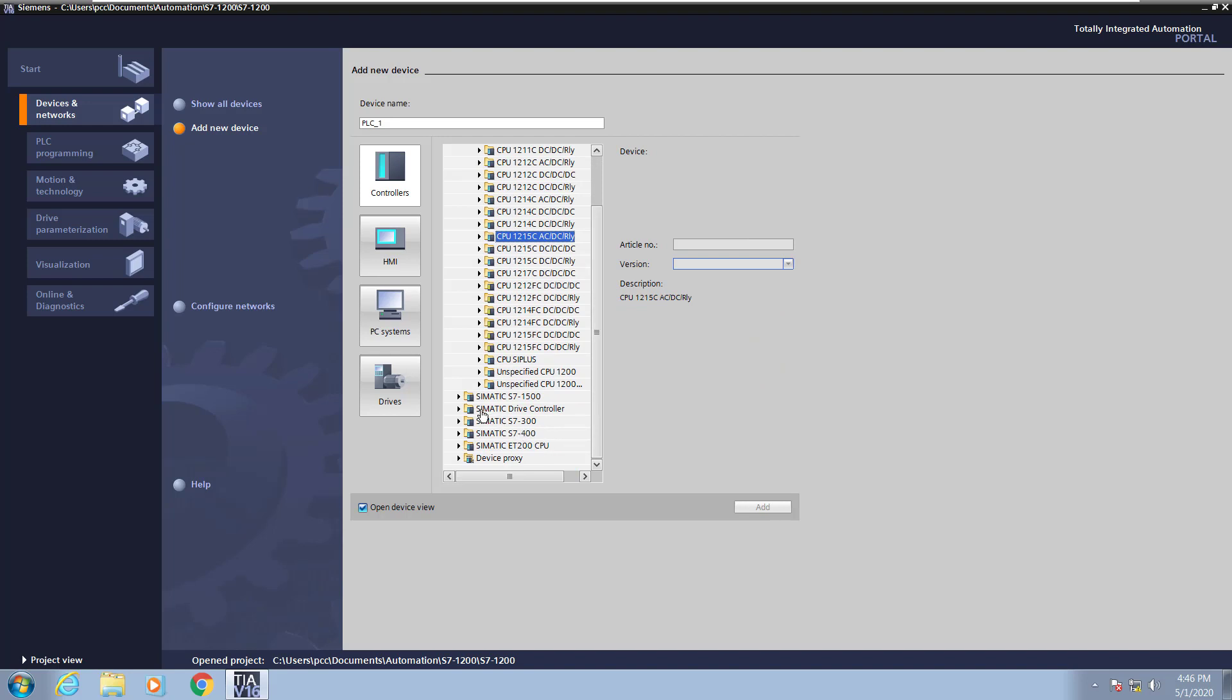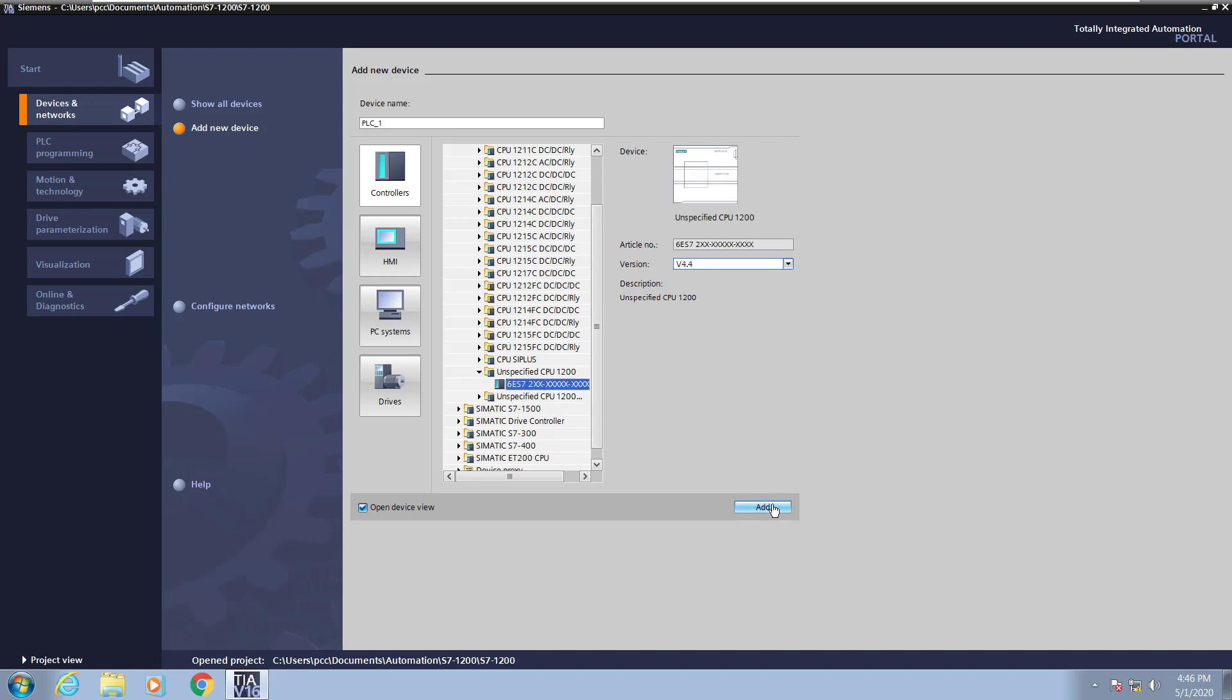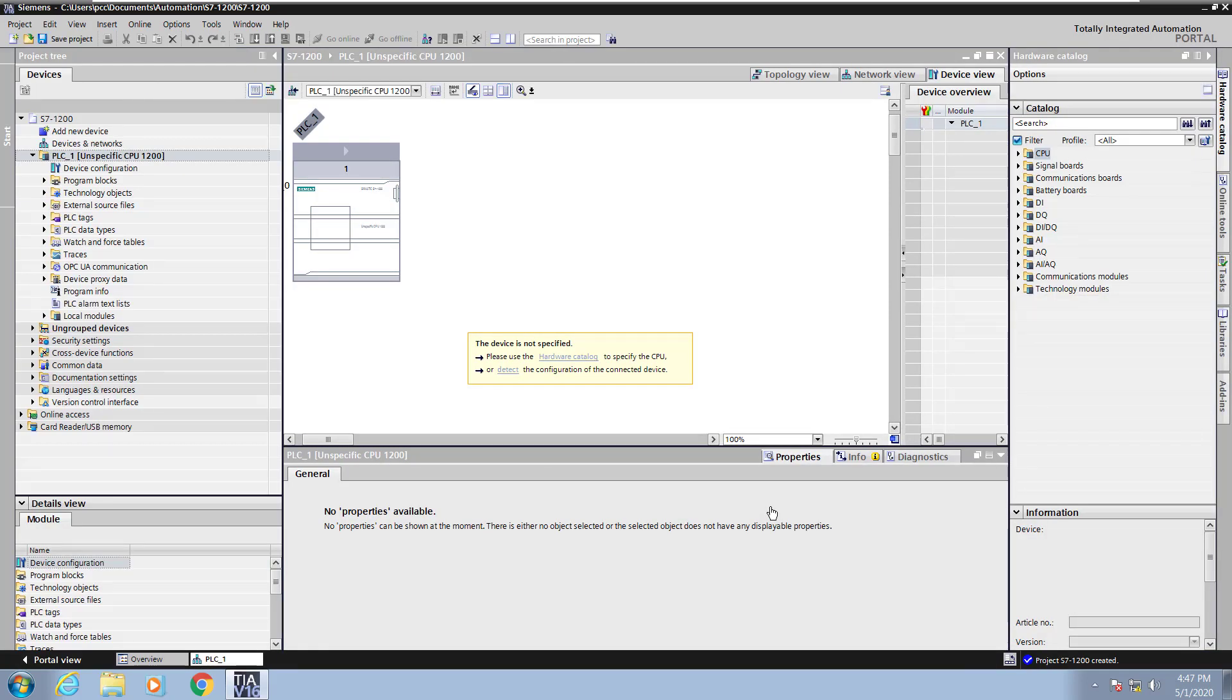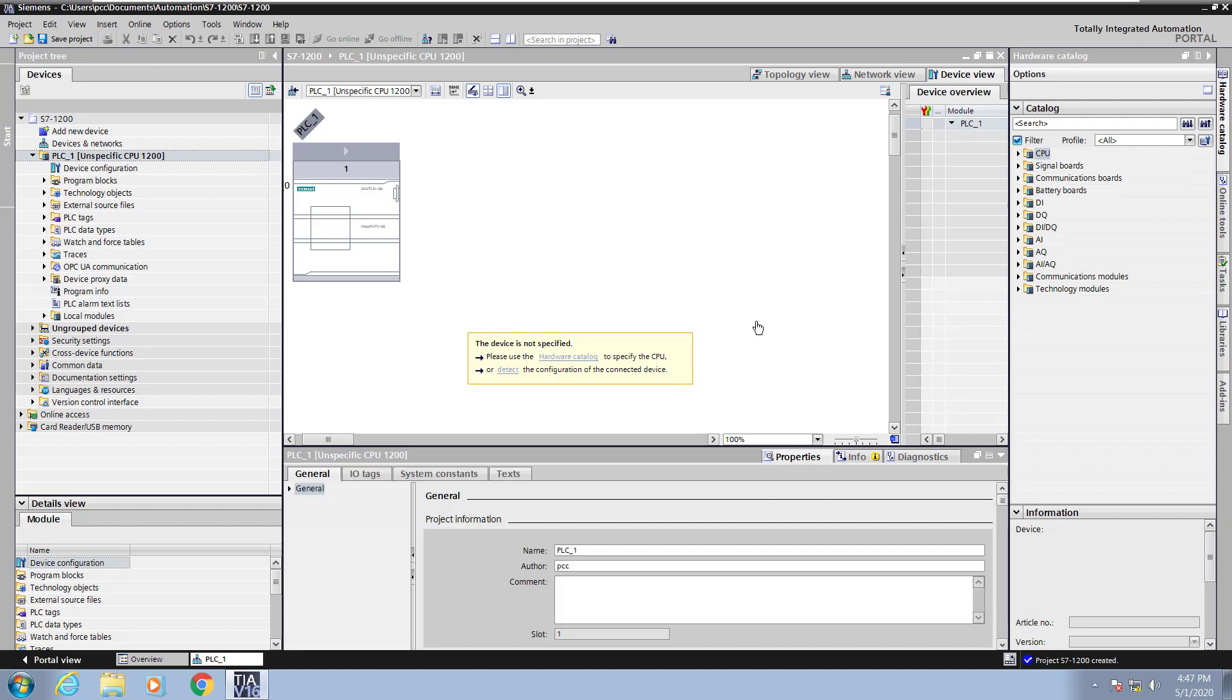I can use an unspecified CPU when my PLC is already wired up and I have power to it so I can detect the hardware configuration automatically. So I'll add the unspecified CPU into my project. You will see that the CPU comes in as a wireframe so it's not a picture of an actual CPU yet. We could in the catalog actually select a specific part number CPU that we'd want to use but what I'm going to do is select the detect feature.